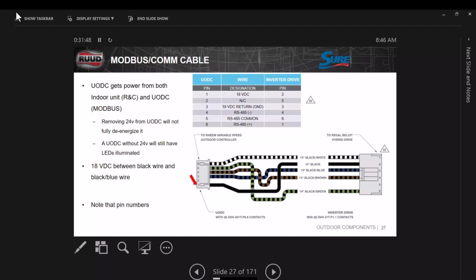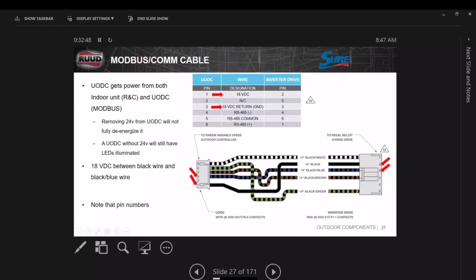So looking at the different wiring configuration, you can see that the 1, 2, 3, 4, 5, 6 starts here, and 1, 2, 3, 4, 5, 6 starts at the bottom there. So if we go to terminal 1 on this board, it goes to number 2 on this one. So on this one, we're going to measure 18 volts DC. 3 goes to number 3 on the board, and that is our 18 volts return back to the other board. Number 4 is the RS485 connection. That's the negative side of the bus. And then number 5 is our common side of the bus, and it's number 6.